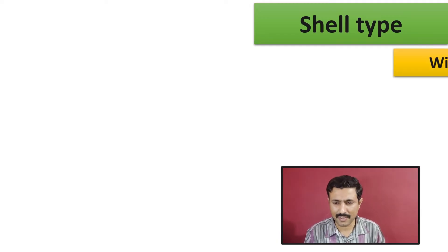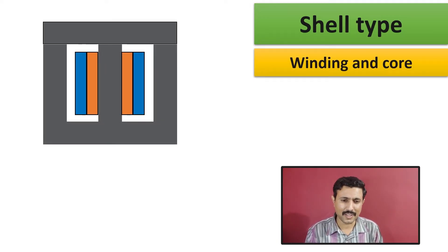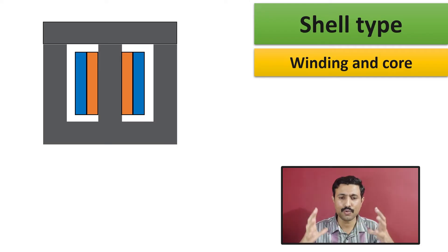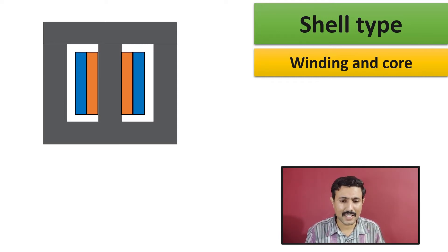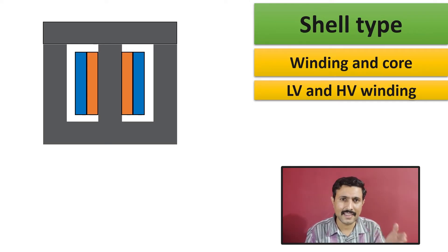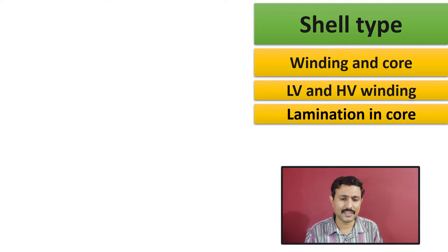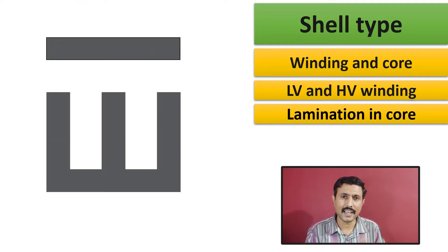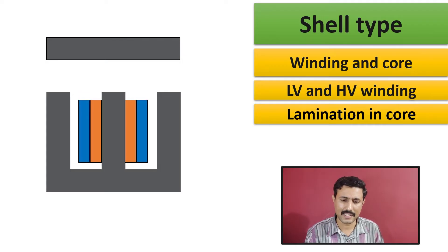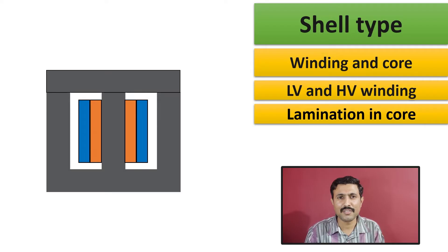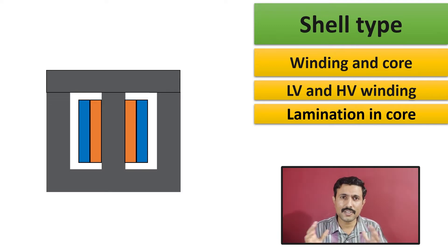Now we'll see the shell type transformer. In shell type transformer, the winding is on the inside and the core is on the outside — the opposite of core type. In shell type transformer, LV winding is inside and HV winding is outside. The lamination material used in this core is E and I shaped, so EI lamination is used in shell type transformer. Initially the LV winding is wound and then the HV winding is wound. Then E and I shapes club together to form a shell type transformer. This is what is inside the transformer; now we'll see what is on the outside.